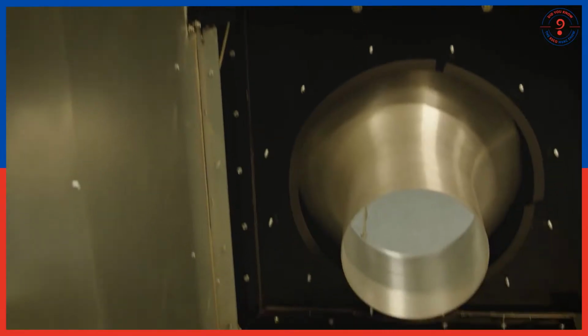And the reason that we use these units to control airflow and static pressure is that the equipment that we're testing, there's very little air pressure drop in our lab. You think about an air handling unit in a real building, it's got ductwork, it's got other equipment that's generating static pressure, building pressures, every variance that you can think of. We don't have that in the lab, so we use this unit to add or subtract static pressure depending on the data point we want to take. So we're not just doing all the testing in a controlled lab environment. We're actually modifying our environment to be able to look at what real world application pressures would look like. Makes a lot of sense. Very intriguing.